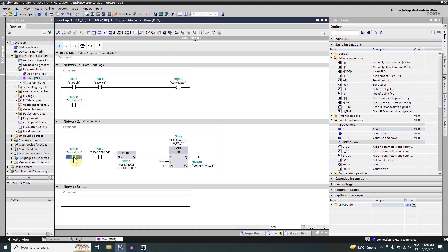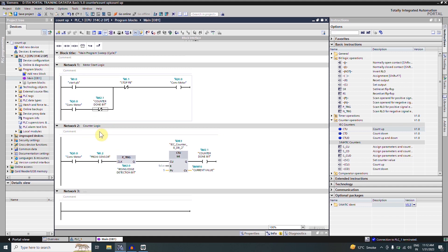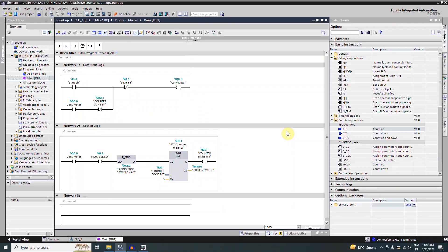The logic is simple: whenever the conveyor motor is running and a box comes in front of the sensor, on every rising edge pulse this counter will be incremented by one. When the count reaches five it will turn on bit M2.1, indicating that five boxes have been counted. We insert the normally closed contact of M2.1 so when five boxes have passed sensor I0.2 this contact opens, stopping conveyor Q0.0. The same bit M2.1 is used to reset the counter and prepare for the next cycle.